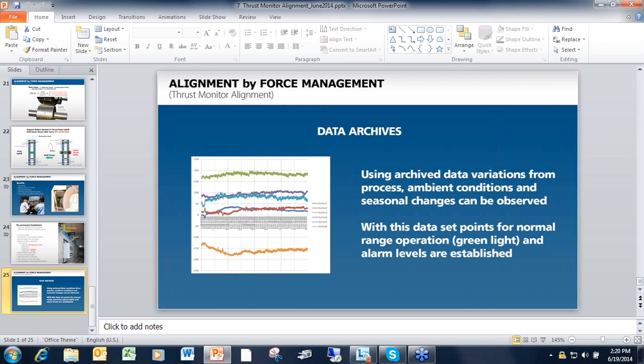As far as the answer to the question is concerned, yes, this is a fully patented system, so I don't mind disclosing all the secrets. It's not vibration, it's not strain. These sensors are nothing more than a simple level. And maybe the word simple is not the right one. This is an extremely highly sensitive level. The whole measuring range is less than 1 degree. It's like 40 arc minutes. And it has a resolution of 1 arc second, which is 1/60th of an arc minute.